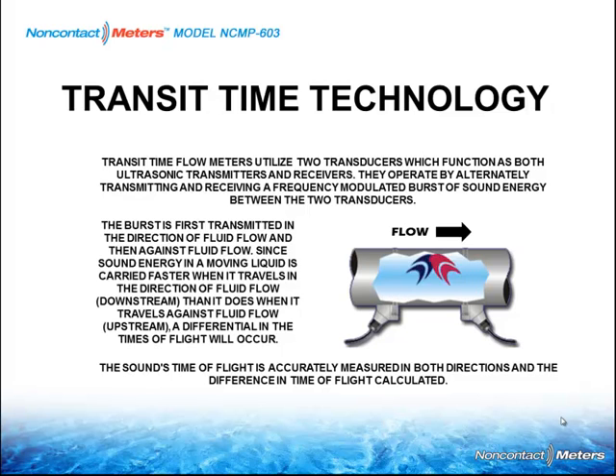So if we were to use this analogy, with this pipe right over here, this would be a bird's eye view, and unlike the man with the rowboat, he would be over here. In this case, we're going to get lazy. We're going to put one sensor here and one sensor here and ricochet off the back wall just because it's easier to see and easier to do and easier to install. So in this case, this sensor sends a sound burst across the pipe, reflects off the back wall, comes downstream to this sensor. We measure how long it takes. Remember again, flow is going left to right.